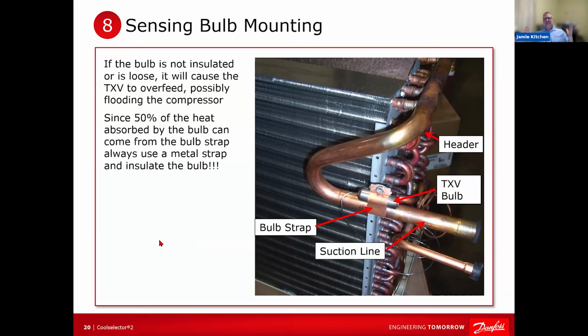All right. So this is an argument that I have. I should say an argument because there's no wrong or right. As a manufacturer, not of the equipment, but of the valve itself, we're always going to wimp out and say, follow the manufacturer's recommendation because we really don't have anything else to say. But if you ask for our recommendation on best practices, we're going to tell you to insulate that sensing bulb because it only makes sense, right?